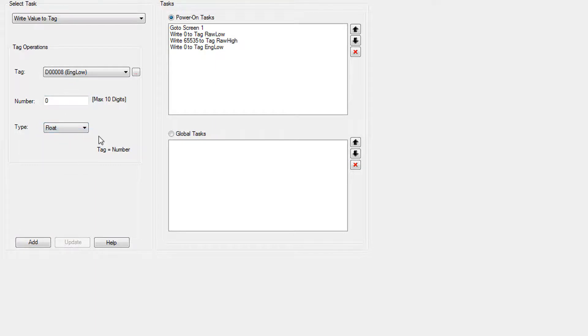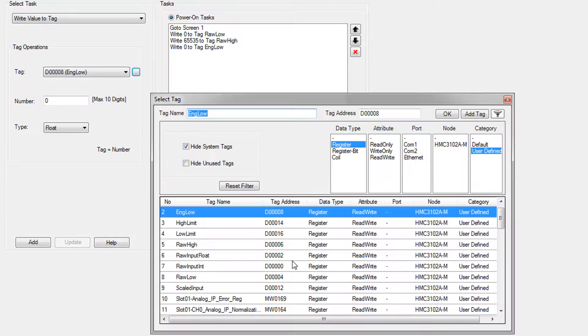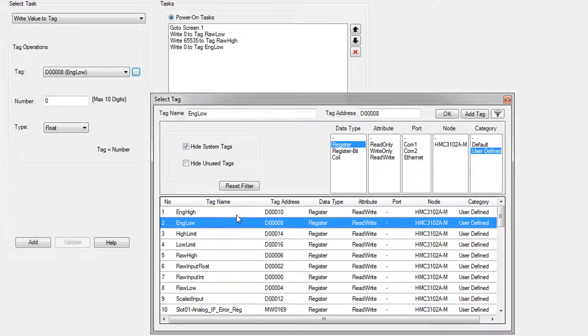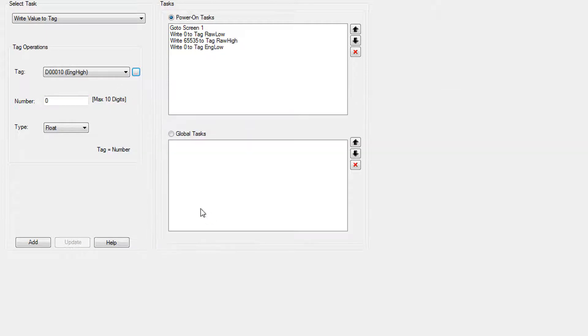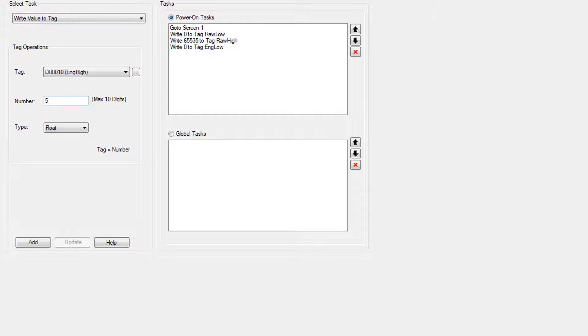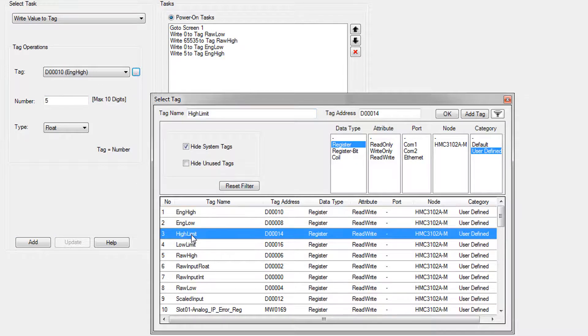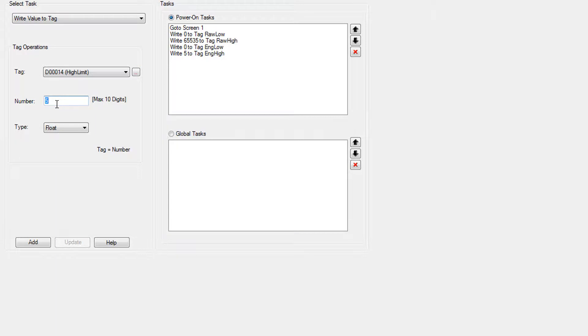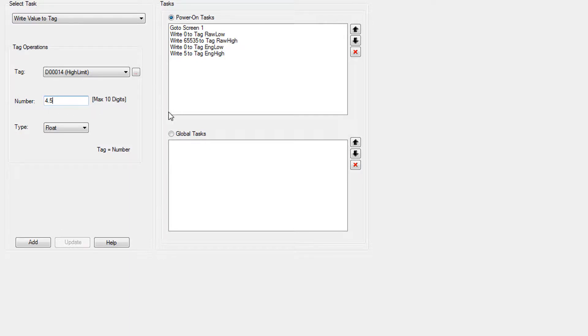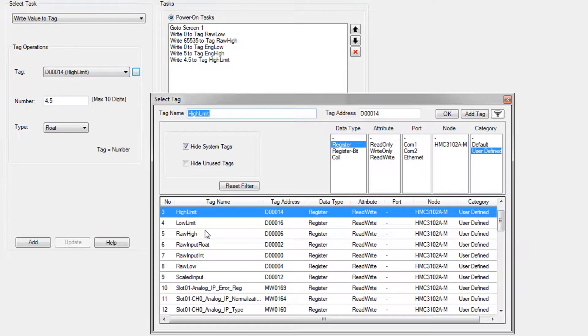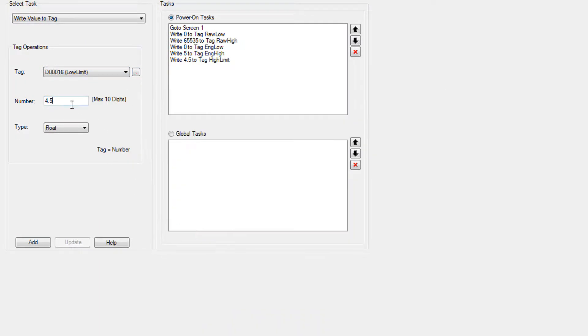And then we're going to do engineering high. The high for the engineering value is five because we're scaling it to be between zero and five because it is a zero to five volt input. And then we're setting the high limit to 4.5. So basically we're going to end up turning on a bit if our input is over 4.5 volts. And then low limit will be 0.5 and add.